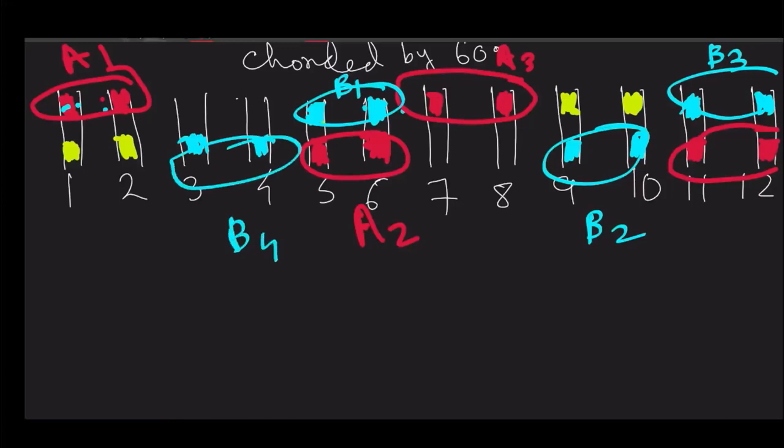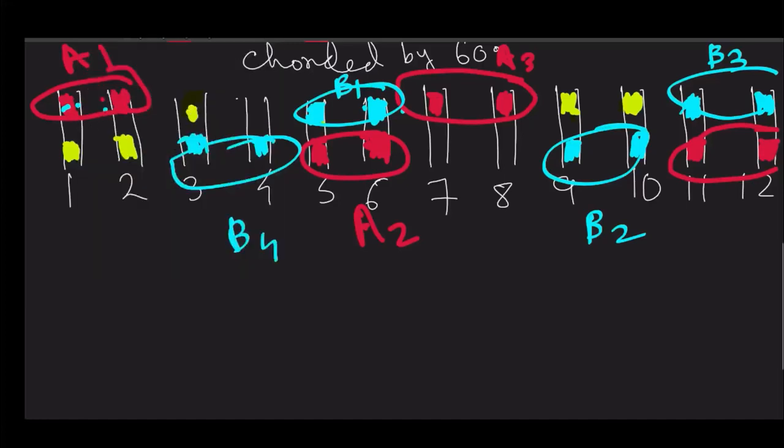Now the remaining should be filled with C. If you place it here, then the other end should be 9 plus 6, it should occupy this slot, 9 plus 6, 15, 15 minus 12 is equal to 3, and 10 plus 6, 16, 16 minus 12 is equal to 4. And for this, again, 3 plus 4, it should occupy 7, and 4 plus 4, it should occupy 8. So you can understand that if you place it in a scientific, technical manner, there will be no chaos in coil placement. It is perfectly easy, perfectly balanced, and you will always get this.